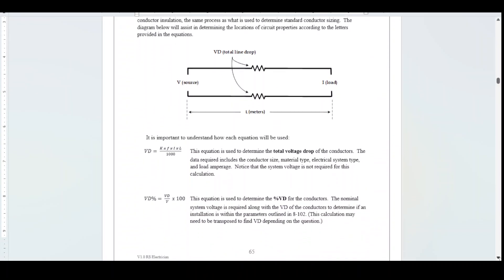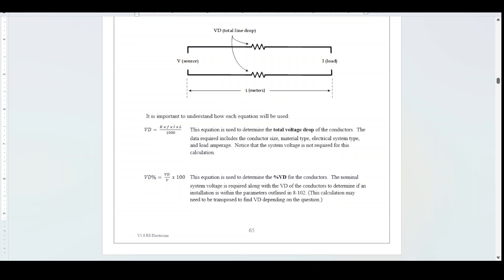It's important to understand how each equation will be used. This tutorial is going to cover all of the equations and examples that use the equations provided in appendix D. This first equation is used to determine the total voltage drop of the conductors. The data required includes the conductor size, material type, electrical system type, and load amperage. Notice that the system voltage is not required for this calculation.